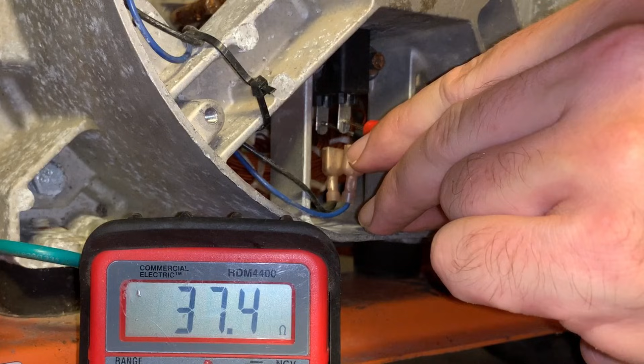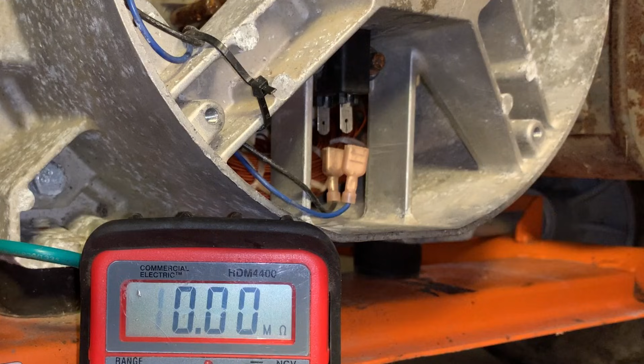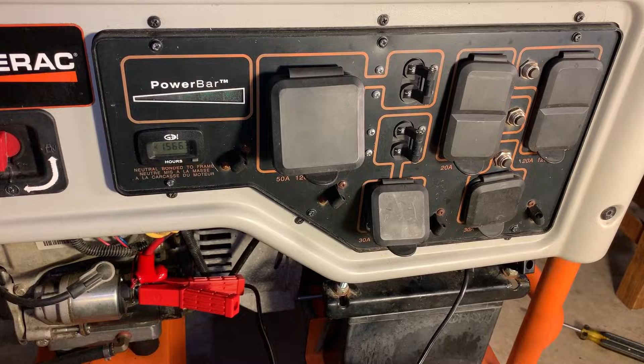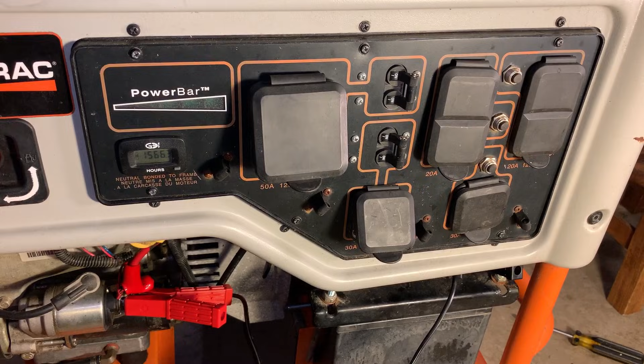Yeah, that's a good reading. That's 37 ohms. So I think the rotor's good, the brushes are good, stator main windings are good. So things are looking pretty positive here. Starting to think that maybe we're just dealing with a bad AVR. On this generator, the AVR, or the voltage regulator for that rotor, is actually behind here, not down on the generator head. So I need to get these screws out, and this panel will come forward a bit so I can kind of get a peek in there and see what's going on.